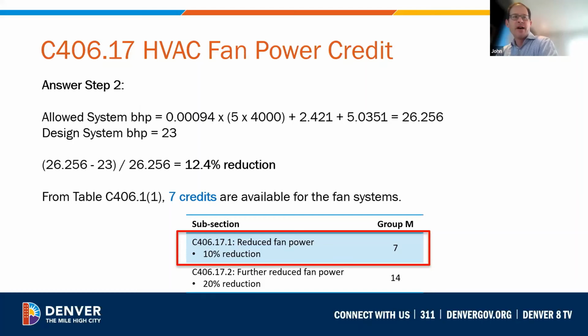If the net result is an allowed system brake horsepower of 26.2, and we have a design of 23, that's a 12.4% reduction. So we can go into the cross section of the table that has that credit, and we can claim 7 credits towards the available credit total for these fan systems. So this is another one. It's certainly design specific, but it's worth checking because the fan power allowances in the code do have, as I mentioned, additional allowances for energy recovery, ducted returns. So it's worth checking to see if your fan system is already exceeding the minimum code requirement.